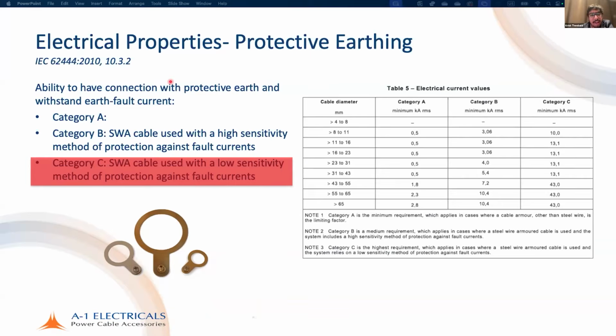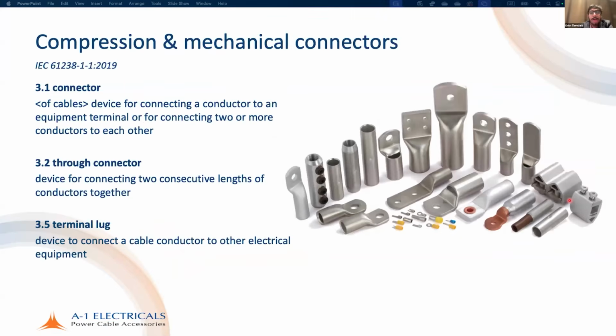They are, and particularly depending on the cable diameter, these are tested. For example, a gland that is able to take a cable diameter of 8 to 11 mm, which is suitable for a simple 2.5 square mm multi-core cable, has to withstand 10 kA of fault current. So these glands have been sent for testing along with the earth tags for this level of fault current. And this is very, very important. So that is it about glands.